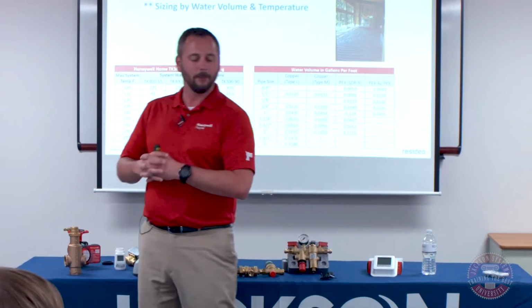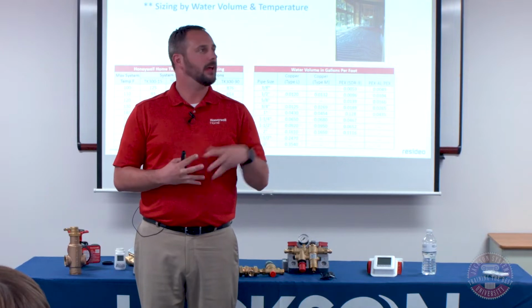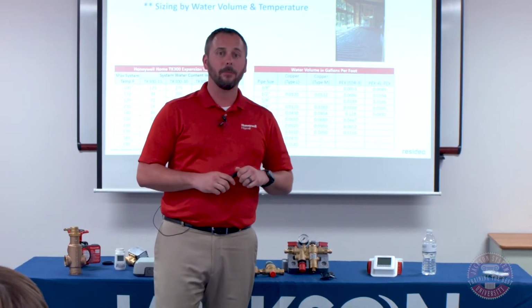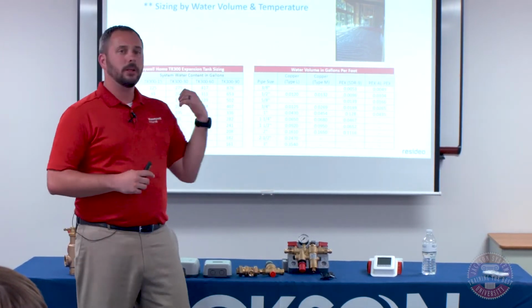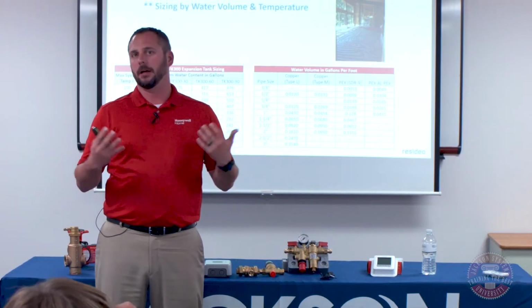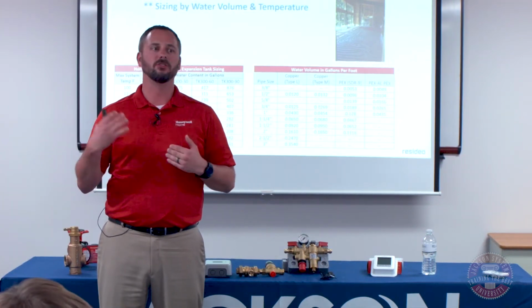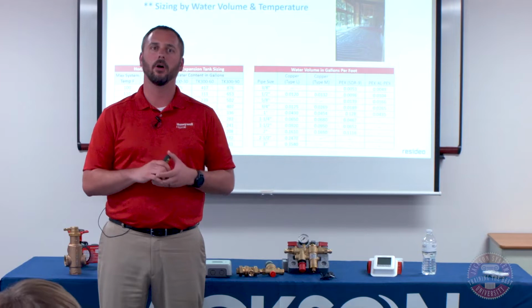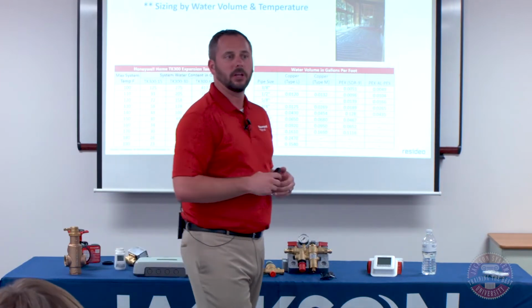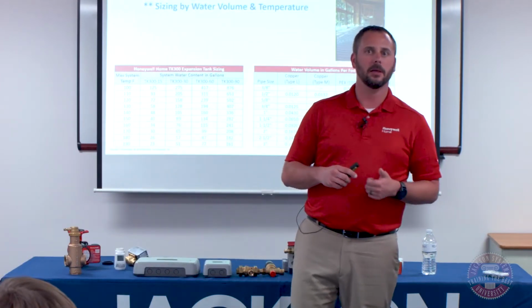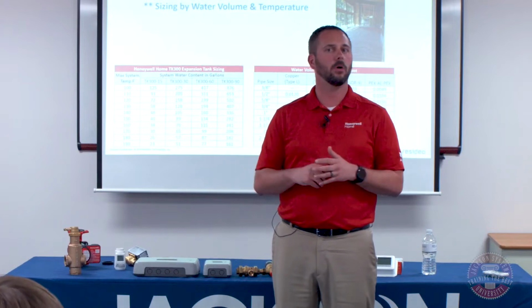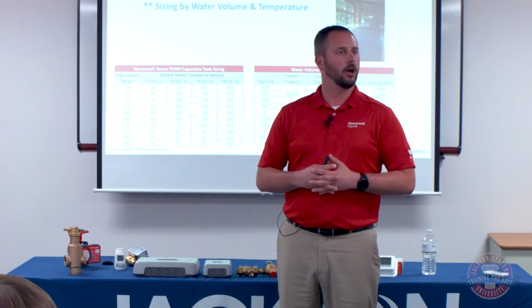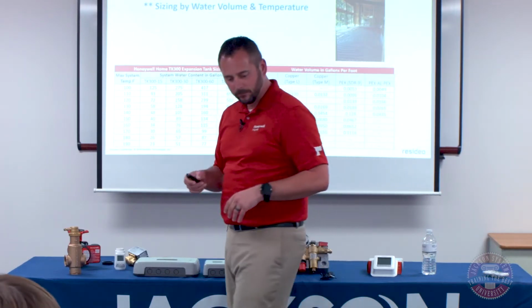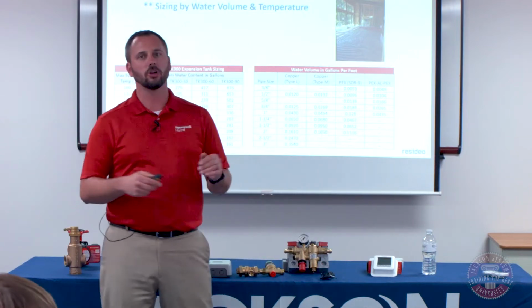Okay. So on the expansion tanks, when it comes to sizing, this is my preferred method. You know how much PEX you bought. If it's radiators or baseboard, you know how much copper is run to them and how much is in there. Everything will have a water capacity on it. Your boiler will have a water capacity size. Your boiler piping will have something there. Just add it all up, ballpark it, see where you're at, and that'll give you an idea. Always go larger if in doubt.